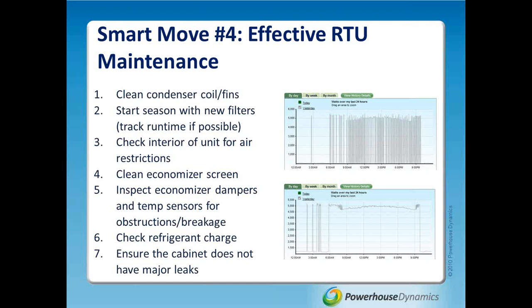One thing I'll mention on this chart is that having real-time data or more advanced metering can be really useful. These two charts highlight two different RTUs having issues. The top one is a unit that's so-called short cycling. That's not an efficient way to run your unit, it will burn out your compressor much more quickly, and it's also less efficient on a kilowatt hour per ton of cooling basis.